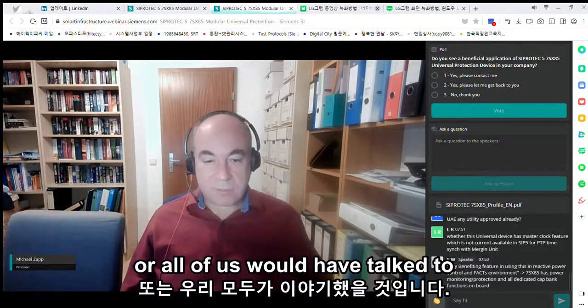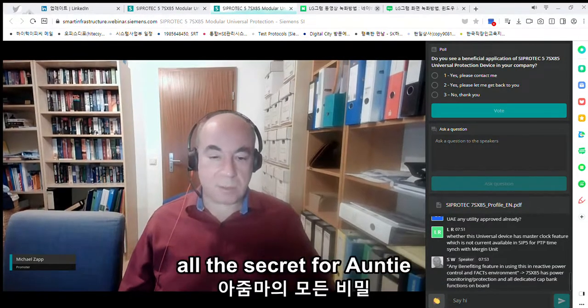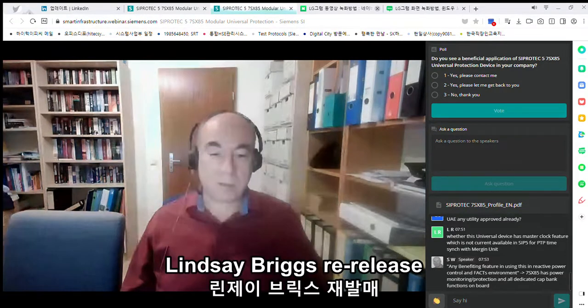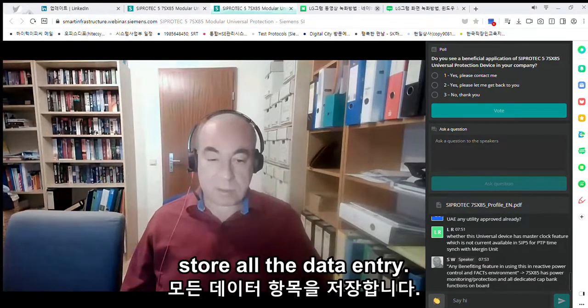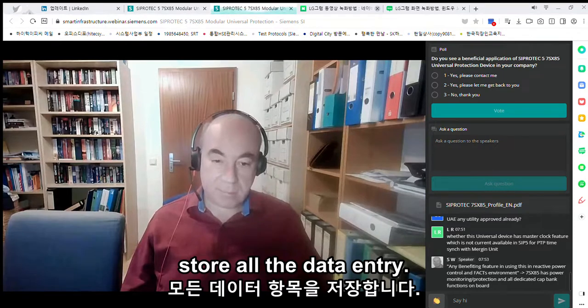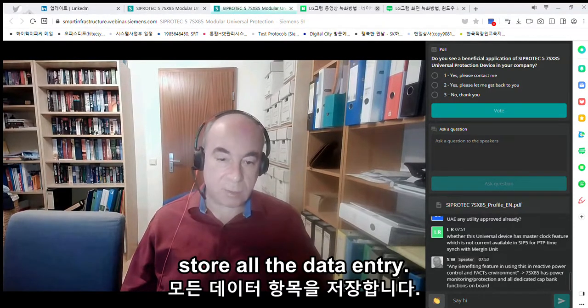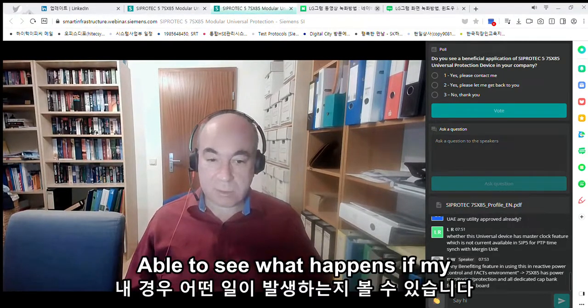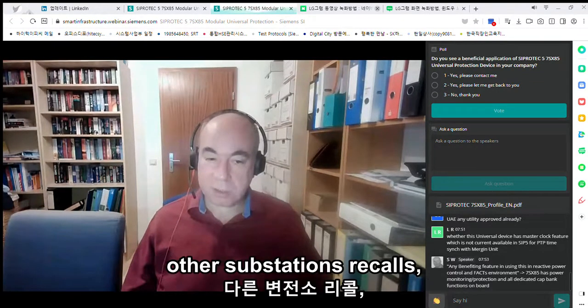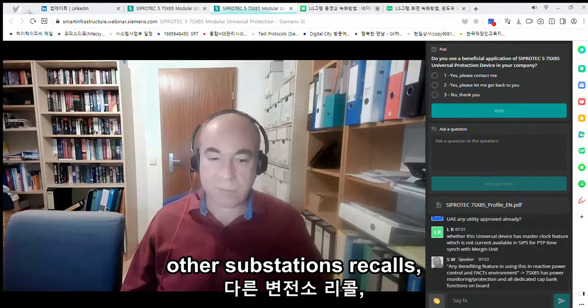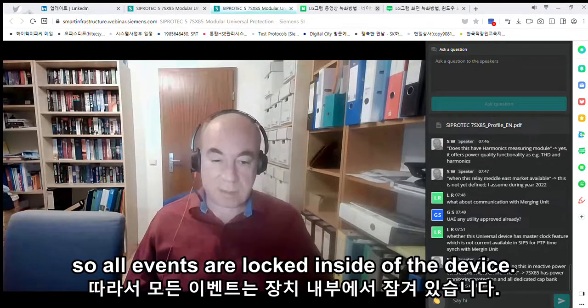Yes, all our SIPROTEC 5 devices, like in the past also our SIPROTEC 4 and even SIPROTEC 3 release, will store all data, what we call sequence of events, to be able to see what happened in my substation, additionally to the fault records. So all events are logged inside of the device.